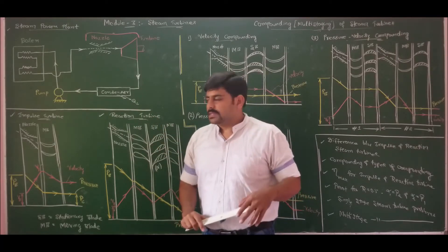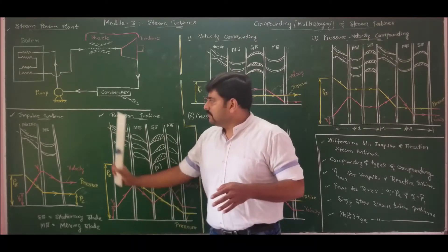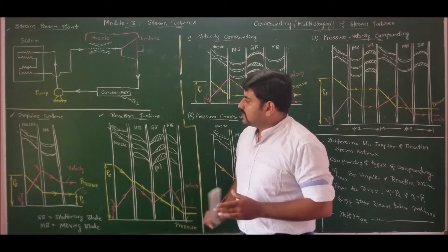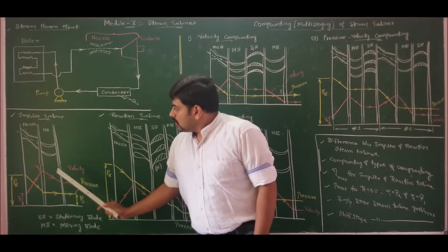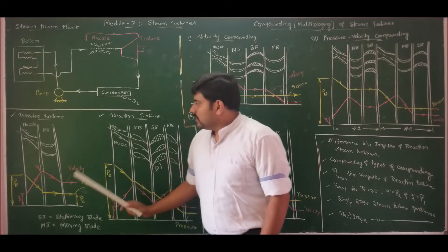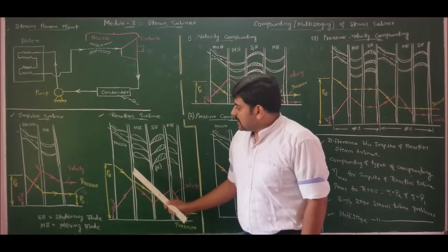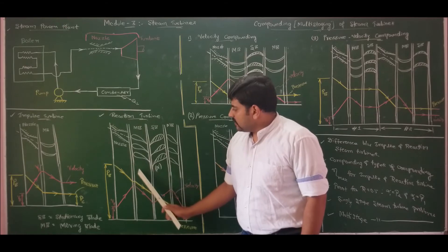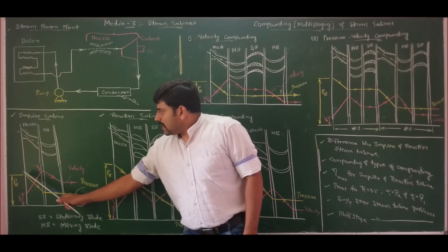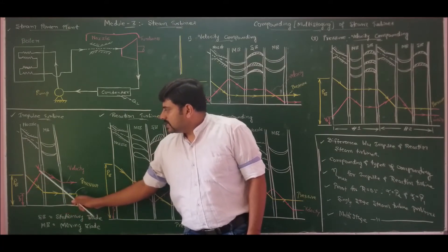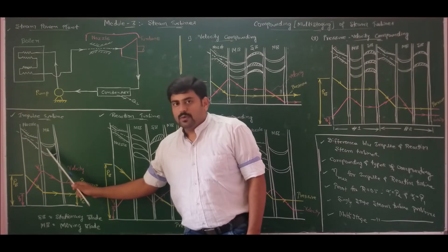Now, coming to the difference between impulse and reaction steam turbines. If you plot the variation of pressure and velocity over the passage length of steam, we observe that steam expands completely in the nozzle in the case of impulse turbine. Whereas for reaction turbine, steam expands partially in the nozzle and the remaining expansion takes place in the moving blades. When steam passes through the nozzle, since a pressure drop is observed, the velocity increases. The exit of the nozzle is the inlet for the moving blades or rotor.